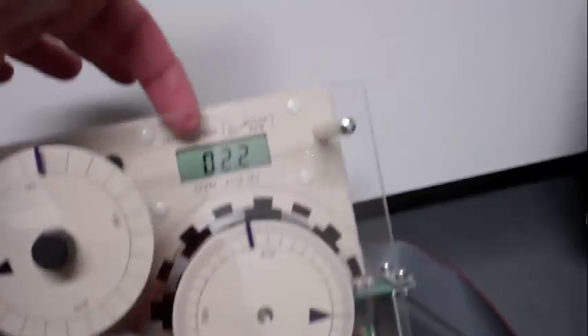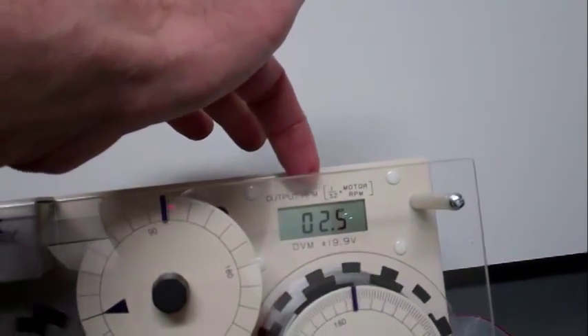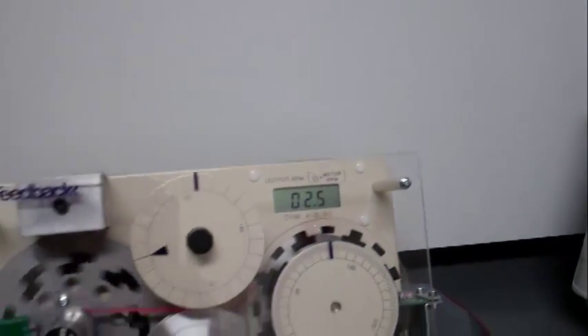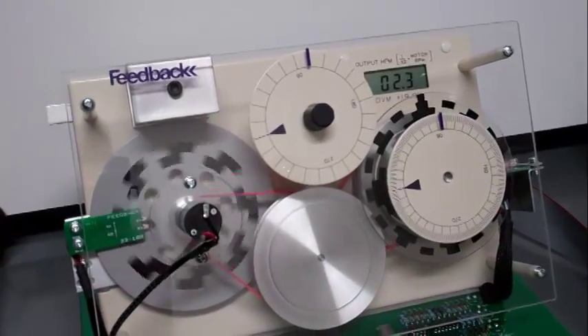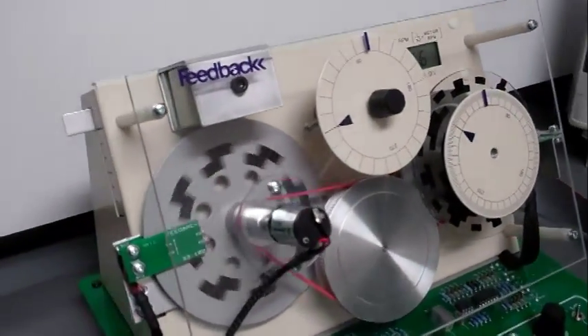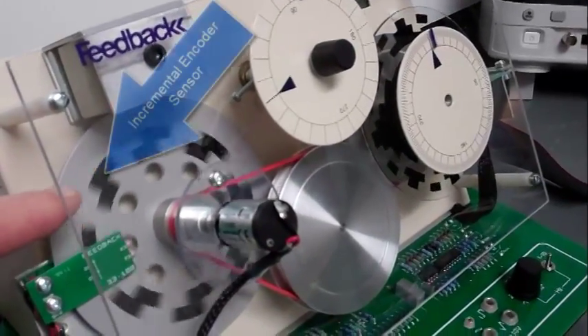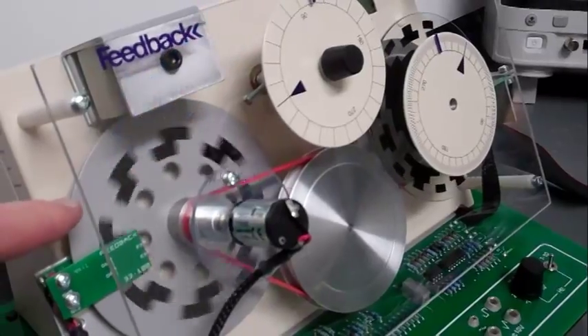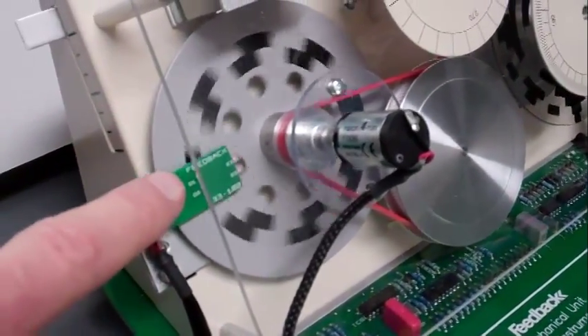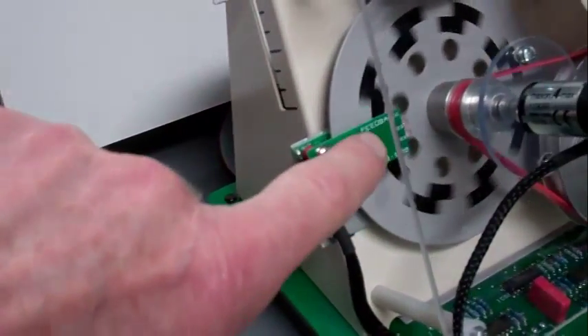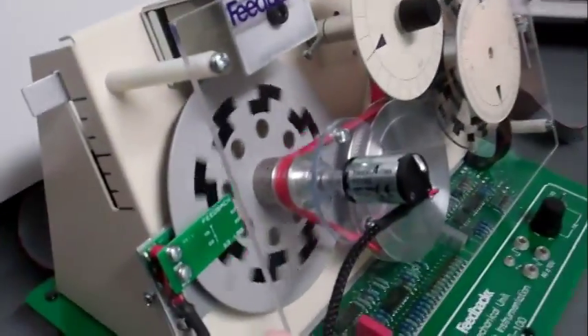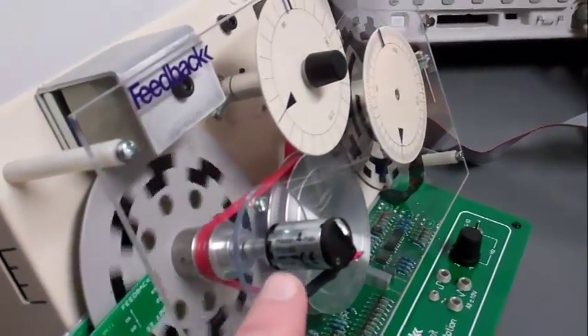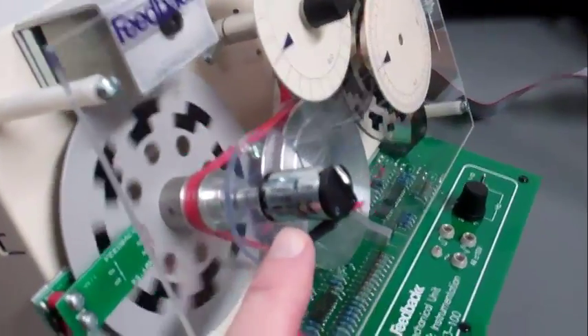The digital display shows the output shaft speed in revolutions per minute. To detect speed and position of both shafts, there are a couple of features. The incremental encoder, the black bands that you see rotating, are detected by the pickup sensor here. The speed is also measured directly with a tachometer, they call it a tachogenerator.